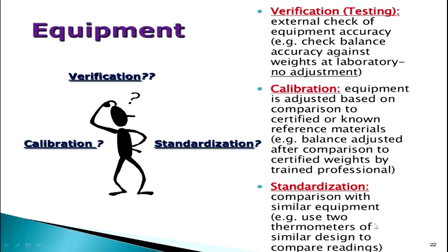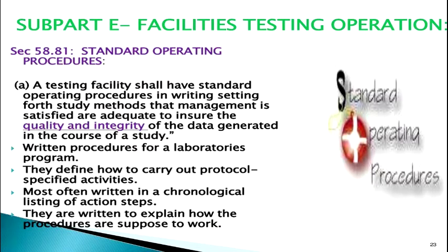Standardization is like comparing two equipments at a time. Say you have two different thermometers of the same company, same maker, and you're measuring the temperature using the two thermometers, and you're looking at whether both the thermometers are giving the same uniform reading. So standardization is always in comparison with a similar equipment. That similar equipment you are choosing for comparison should be well calibrated, or mostly it's a new equipment or less used equipment, so you compare your equipment with that similar equipment.